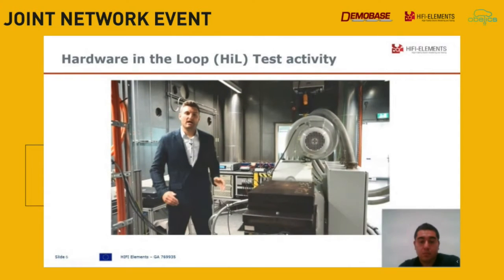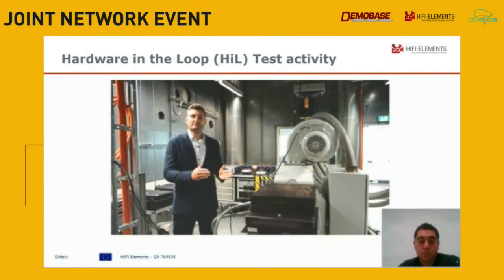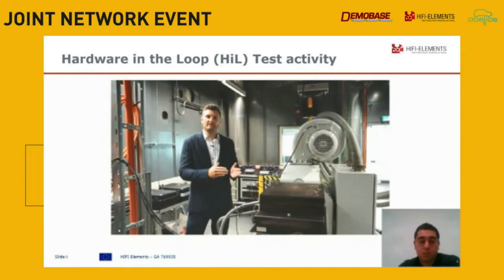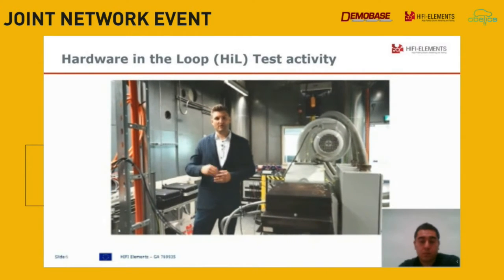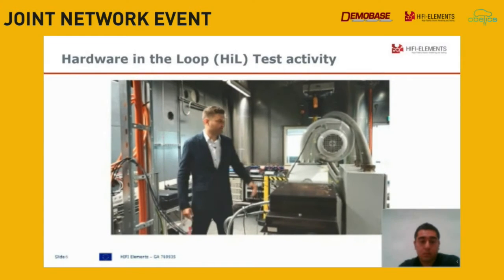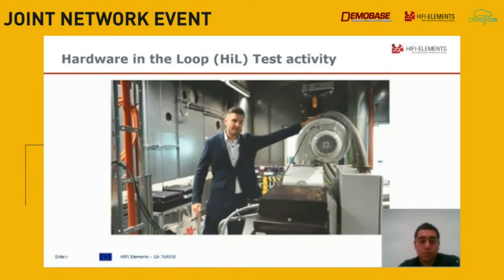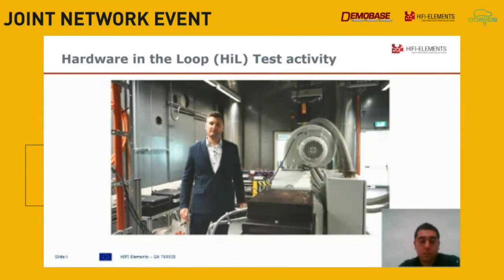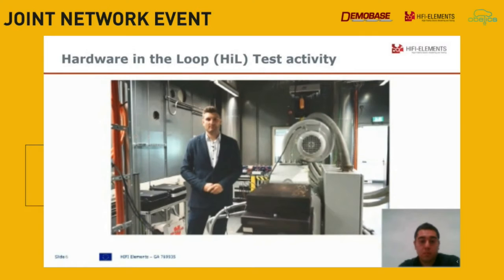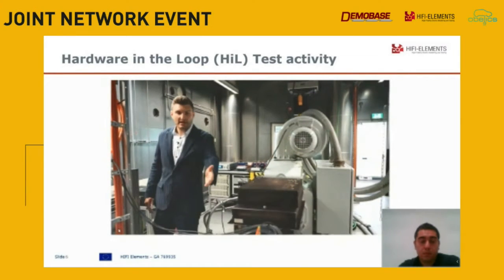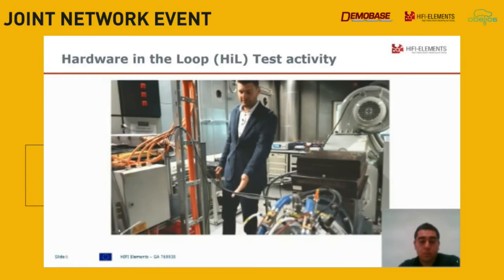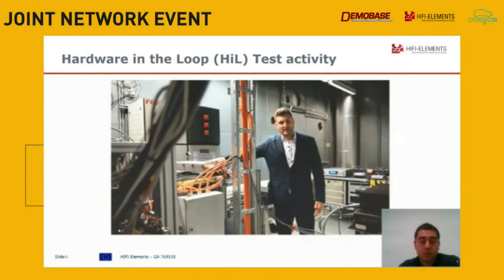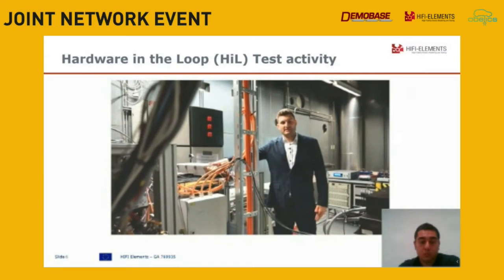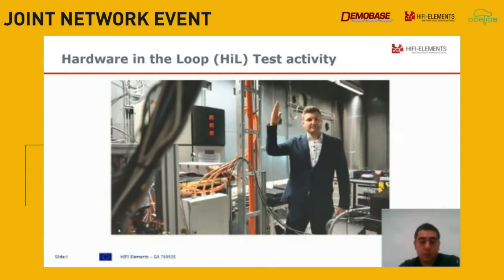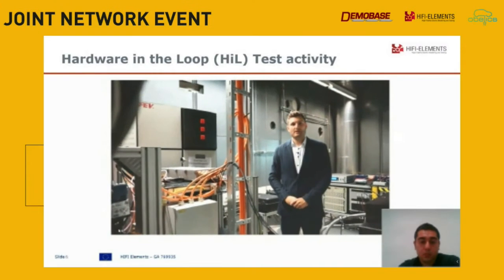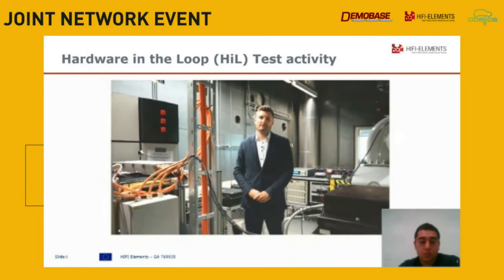Both machines are connected mechanically via a measurement flange, which transmits the measured speed and the measured torque to the test bench automation system outside the test cell. Electrically, the load machine is connected via these gray thick cables to a frequency converter on the upper floor, which also incorporates the speed controller. The device under test is connected via these orange lines to the traction inverter on the AC output, and the inverter is connected on the DC input to a DC sink source on the upper floor as well, which can be adjusted dynamically from 0 to 800 volt DC.